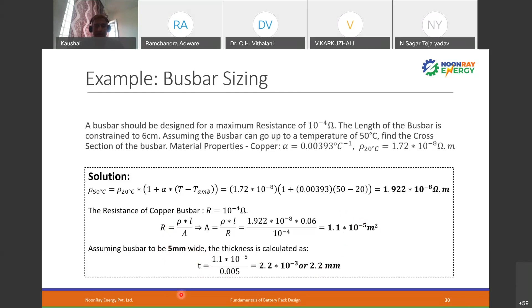Am I right? Then T becomes a constant for me. That is, I cannot go for more than 1 mm. So in that case, to increase the surface area, I have to go for a higher width of the bus bar. From the same calculation, you can find that out.